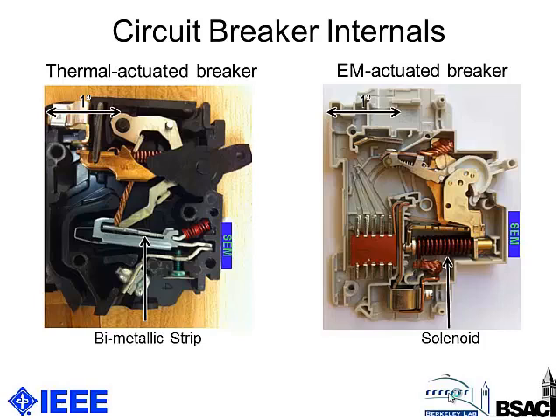On the right, you see what is referred to as an EM actuated breaker. So this breaker has a solenoid inside, and it functions fundamentally different. So when the current through the breaker gets large enough, the magnetic field concentrated by the solenoid gets large enough, and eventually a Lorentz force is strong enough to pull in a lever and actuate the circuit breaker. So for clarity here, I've annotated where our SEM sensor would be placed on these breakers.